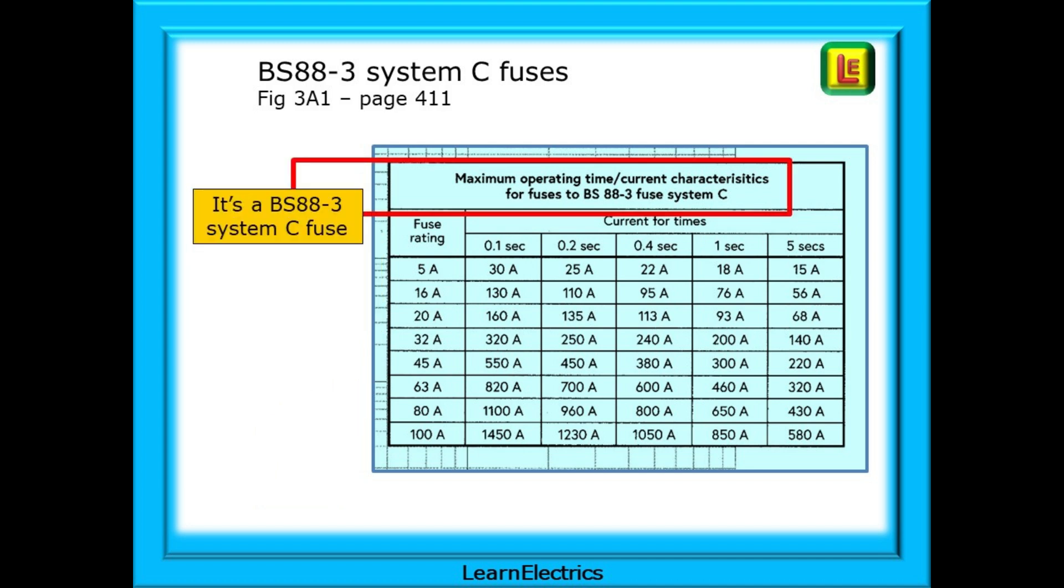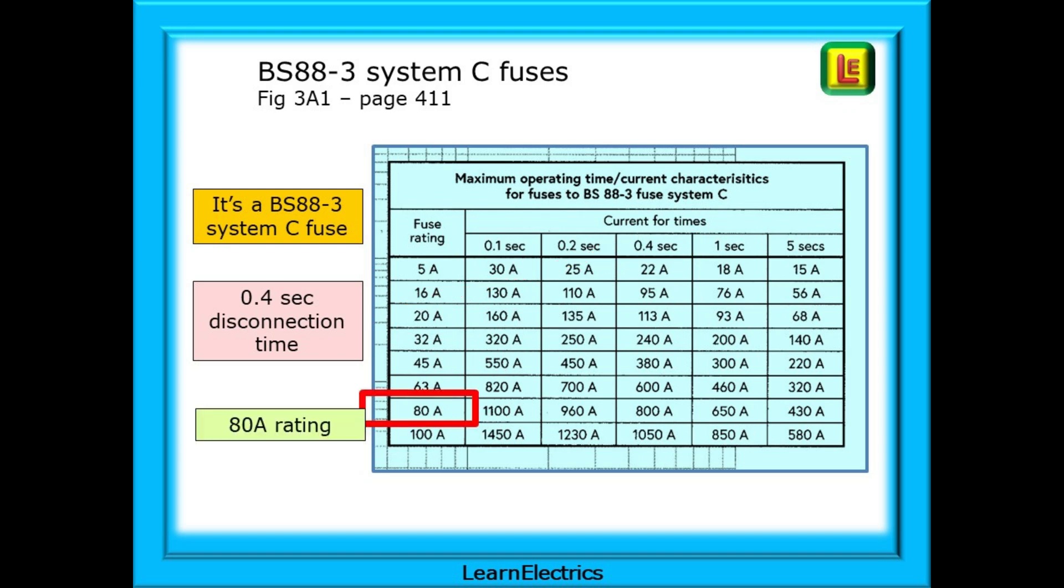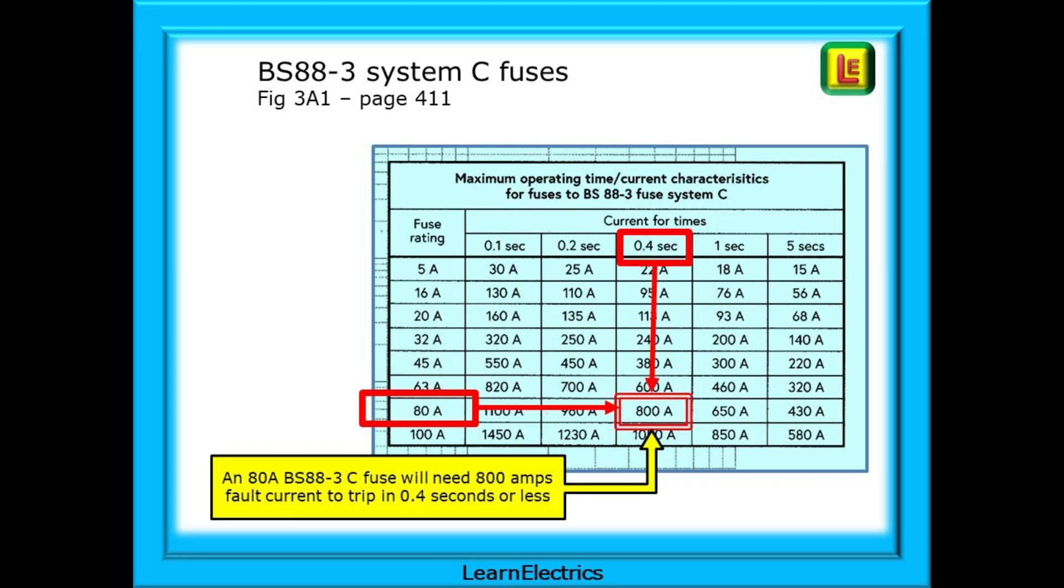Let's work our way to an answer. We have the correct table. The heading tells us that this is the chart for BS88-3 system C fuses. Make sure that you are starting out with the correct chart, the correct information. We need data for a 0.4 second disconnection time. So find the appropriate column and follow it down. On the left hand side of the chart is the available fuse ratings. Find the row for 80 amp fuses. Where the 0.4 second column and the 80 amp row cross each other is the answer that we need for the calculation. An 80 amp BS88-3 system C fuse will need 800 amps of fault current to trip in 0.4 seconds or less.